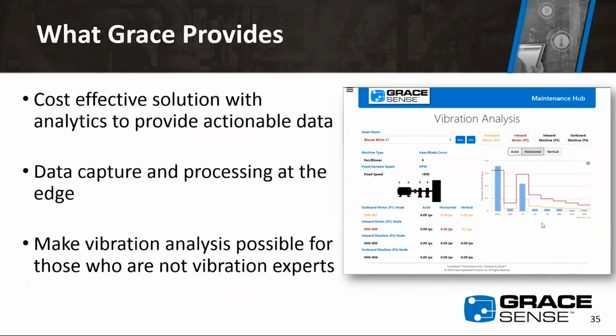On the right is our vibration analysis suite. You can go in and quickly set up an asset by choosing what type of machine it is. In this case it's a fan or blower, but maybe it was a direct-driven fan or a compressor, and this changes the ISO values we look at to determine if it's healthy or not. You can also input other system information, like what speed it's running at, to help get the analysis done correctly.